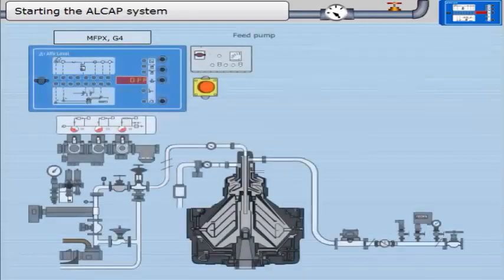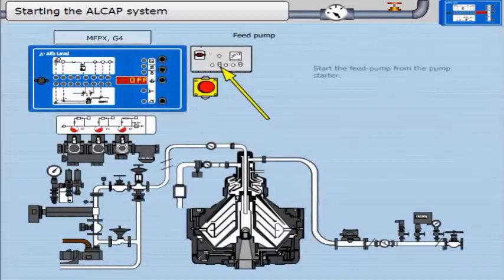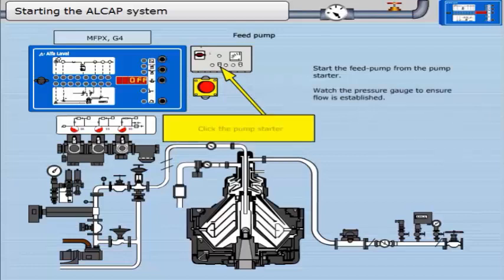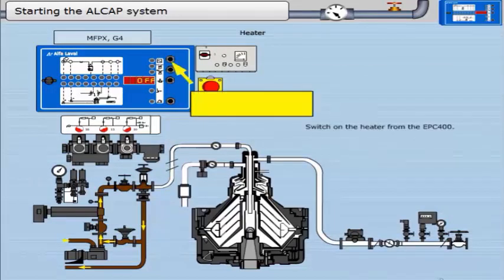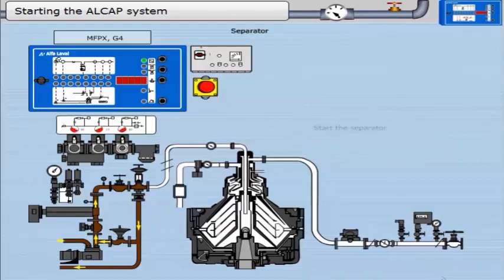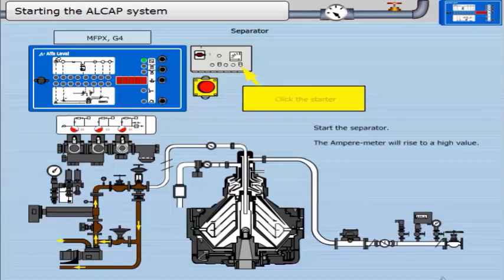Starting the ALCAP system. Start the feed pump from the pump starter. Watch the pressure gauge to ensure flow is established. Click the pump starter. Switch on the heater from the EPC 400 — click the button. Start the separator; the ampere meter will rise to a high value. Click the starter.